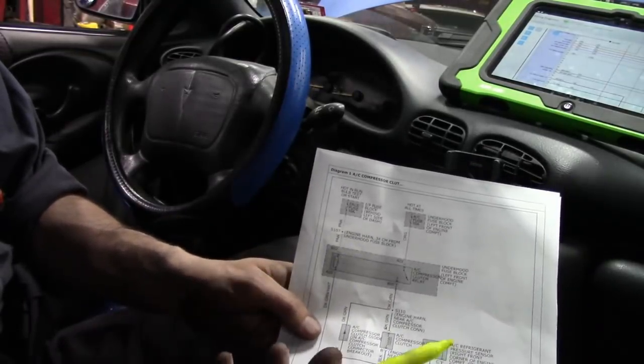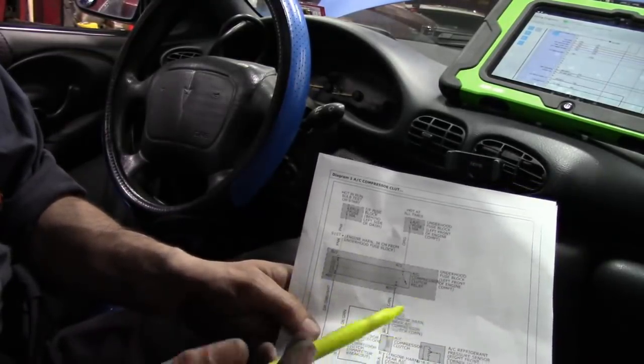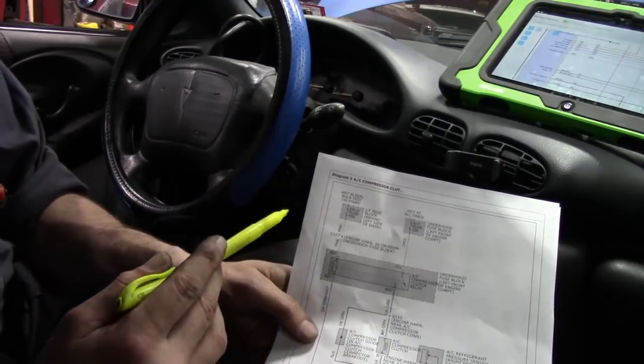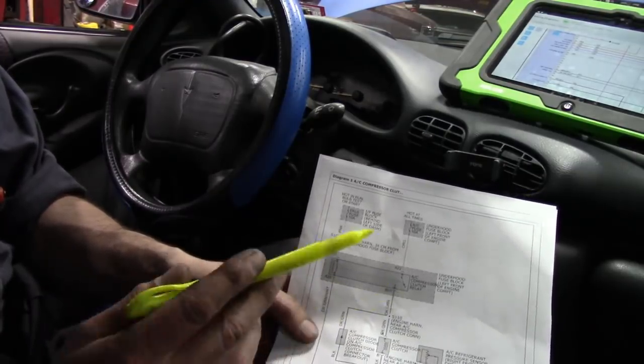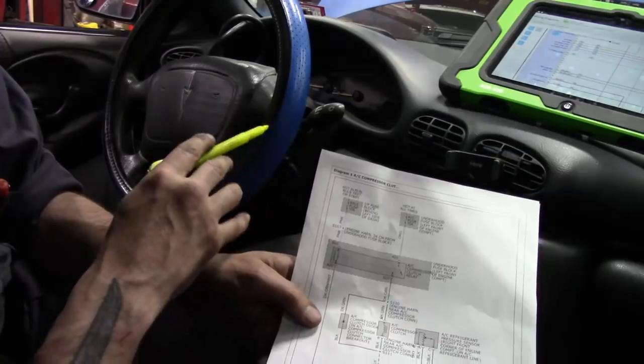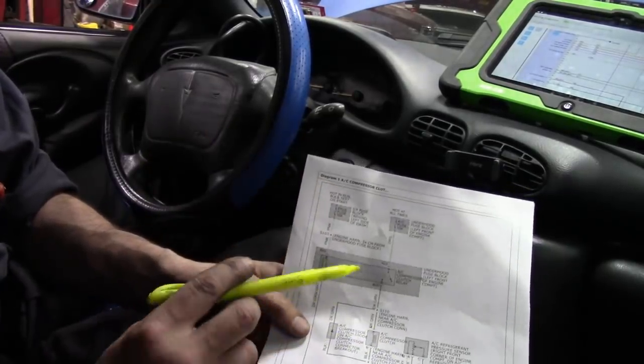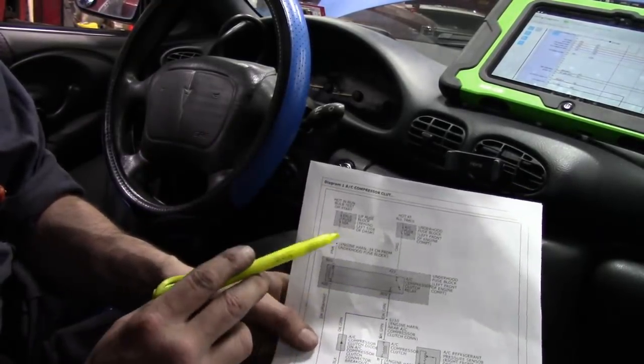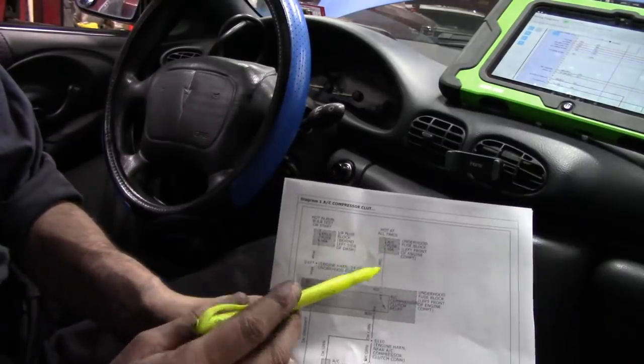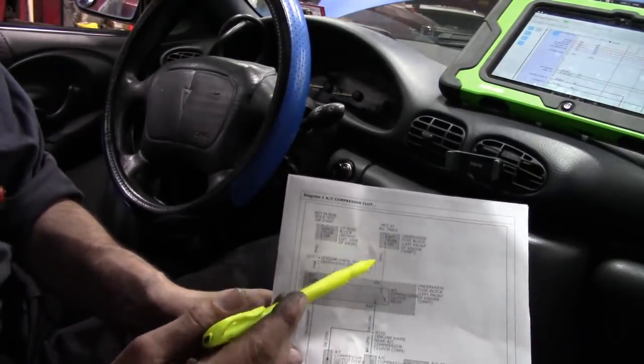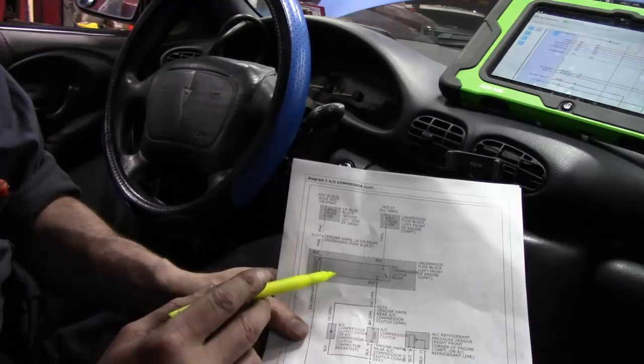So are we at a freon issue, or is there something else going on here? I already knew what direction I'm going. I'm going to the AC sensor first to check the circuit. It's a 3-wire sensor, but I just wanted to verify fuses — they're easy enough to check, right? Fuses are good. Go to the relay.